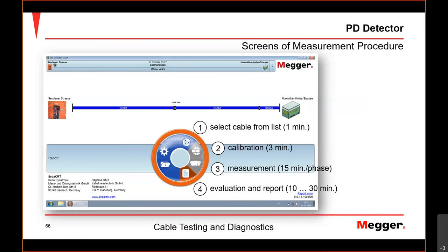Because you can have three bad joints on the same cable and you will see all three bad joints. And then you have pulses that overlay and run into each other, and then you need to judge, is this a reasonable pulse or should I rather ignore this because it's not really identifiable. Software will do that very nicely, but there are always these cases where you say, well, a human should have a look at that and confirm that it's okay. So that's basically the procedure.